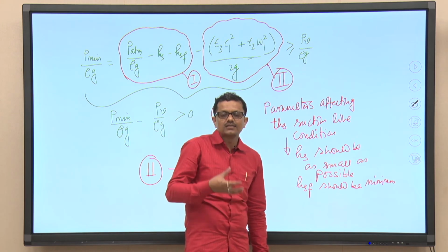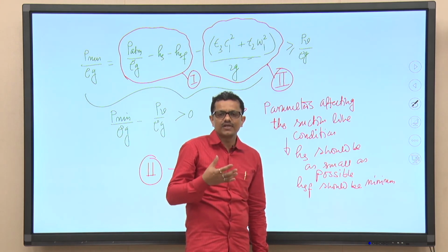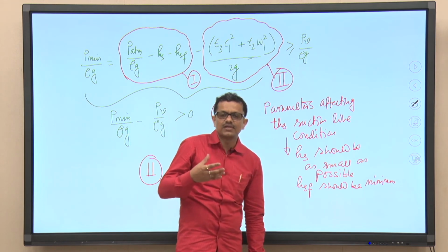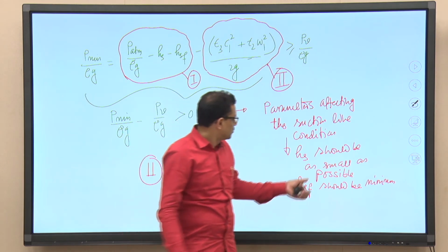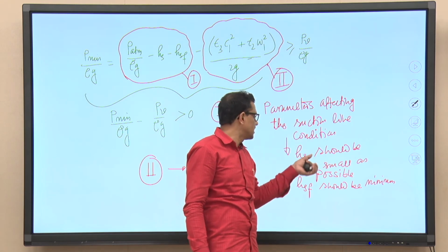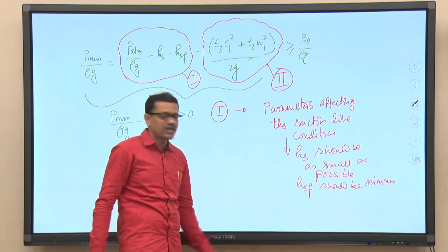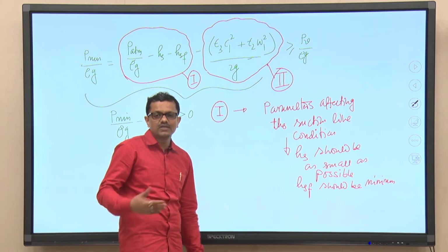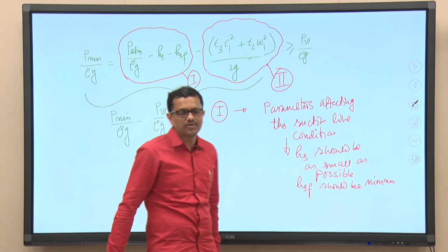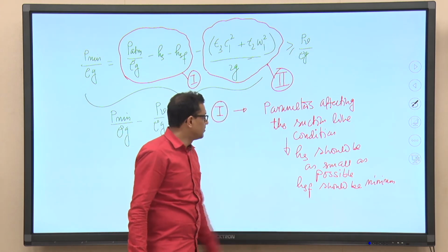So, suction side system design is very important. We will discuss the pumping system design in a separate class. From the perspective of cavitation, the static height of the suction line, as well as frictional effects due to valves, bends, and transport of liquid through the pipeline, should be minimum.